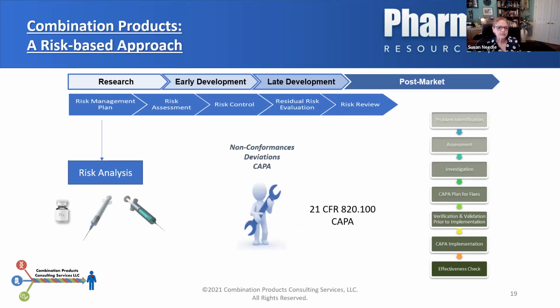You could be looking at non-conformances, at deviations, and even corrective and preventive actions. Your corrective and preventive actions is one of the called out provisions under 21 CFR Part 4. So when you realize that it's a called out provision, you start to realize it's tied hook, line, and sinker to risk management. So it's part of the risk-based approach that the FDA has called out when they put Part 4 in place. So I've got to go through my very methodical application of CAPA, of problem identification to risk assessment, root cause investigation, and then planning for real root cause fixes, verifying and validating those root cause fixes before I actually implement them, and then ultimately implementing them and verifying that they are effective. That is the very methodical approach you're expected to take under 820-100 for CAPA. And like I said, it's part of the risk-based approach.